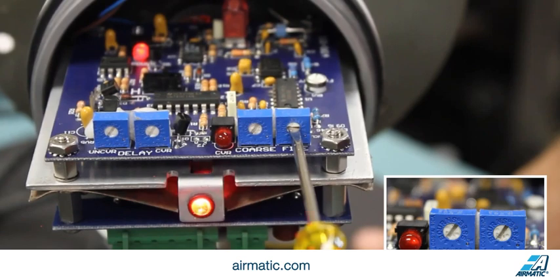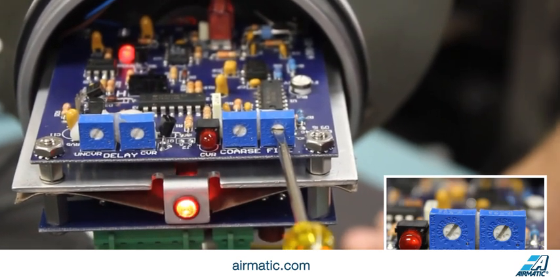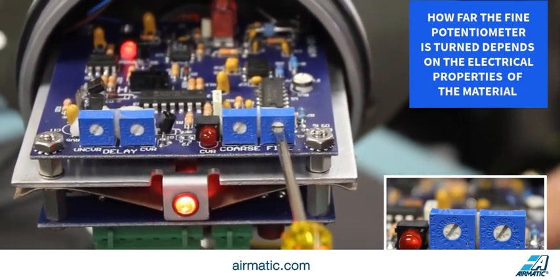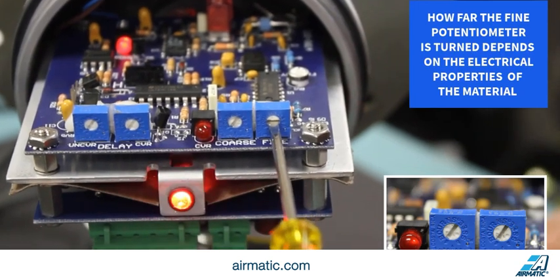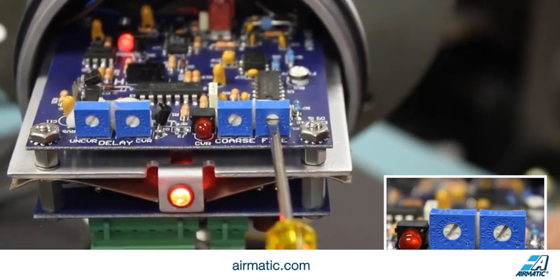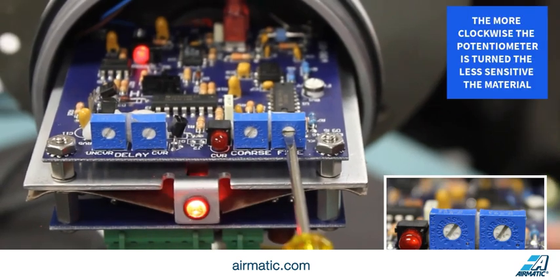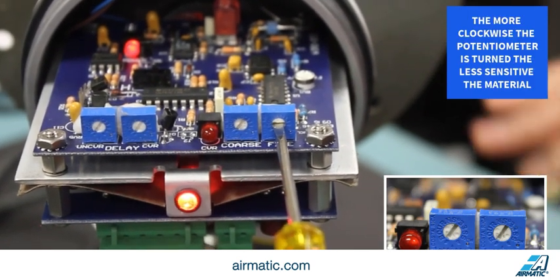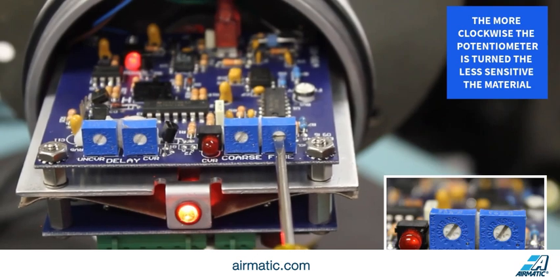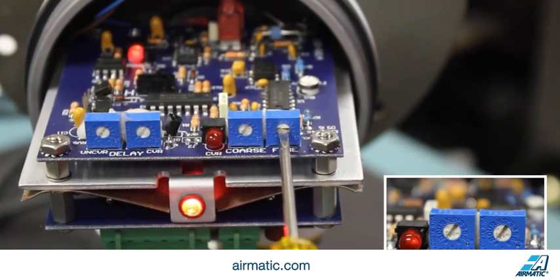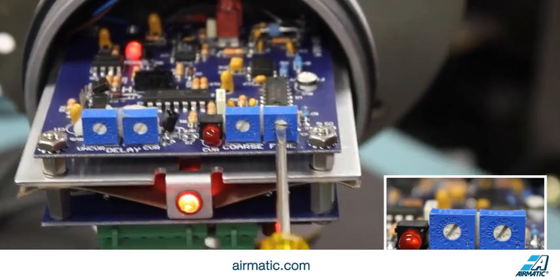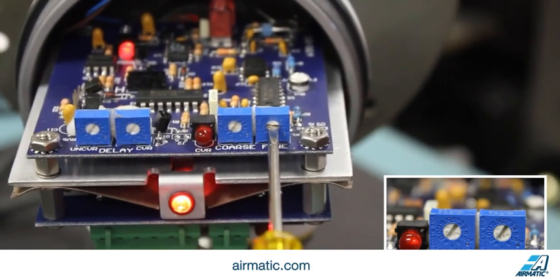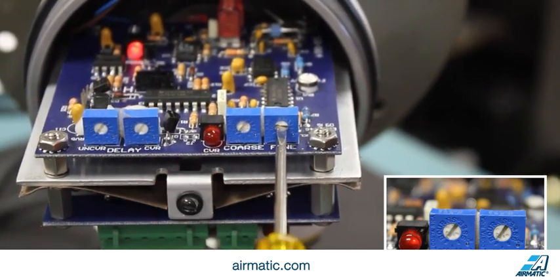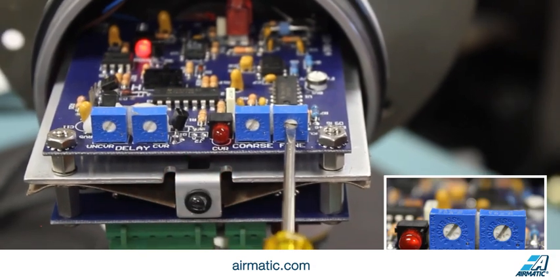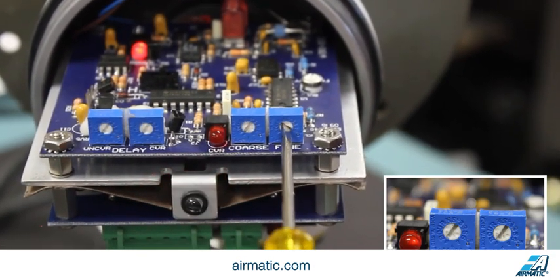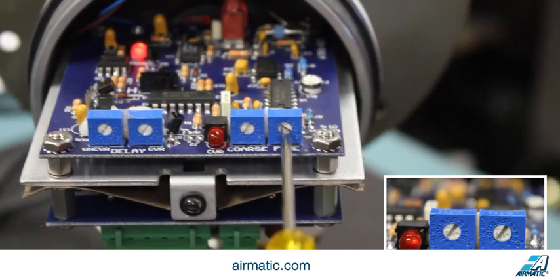Now, how much further clockwise we turn the fine potentiometer is dependent on the electrical properties of the material you're trying to sense. The more clockwise you turn it, the less sensitive it's going to be, so it's going to need to see a greater change in capacitance in order to show covered. For a high sensitivity, if you have a hard to sense material, you'll turn it about a 1/16 of a turn, which is about a half hour to an hour on a clock face. So we'll turn it that much further clockwise.